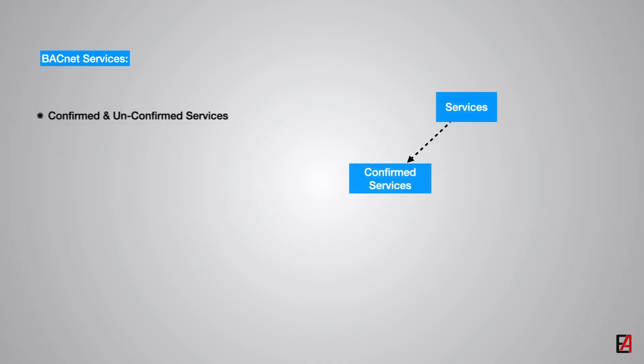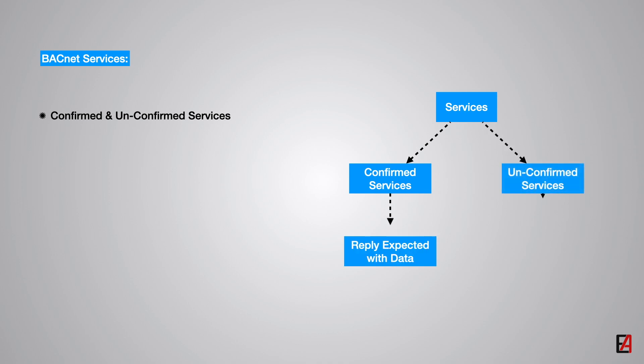There are two categories of services, confirmed services and unconfirmed services. In confirmed services, a reply from BACnet device with data is expected by the requesting device. In unconfirmed services, no reply is expected from the BACnet device.